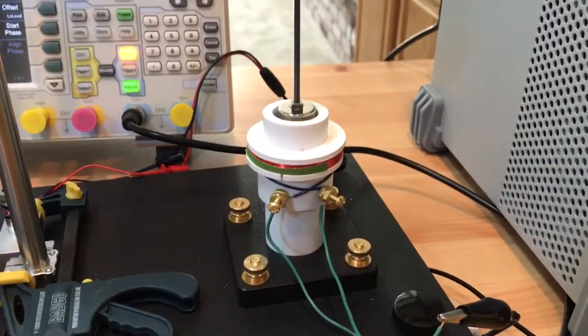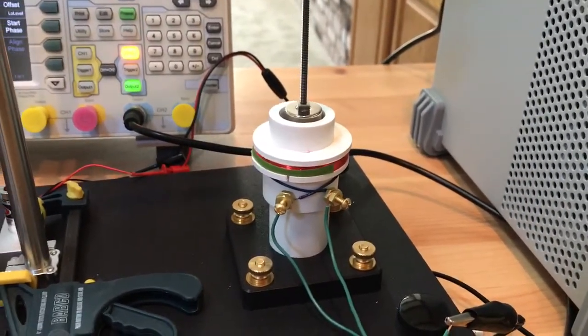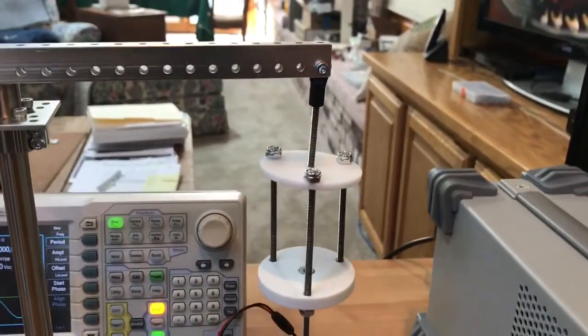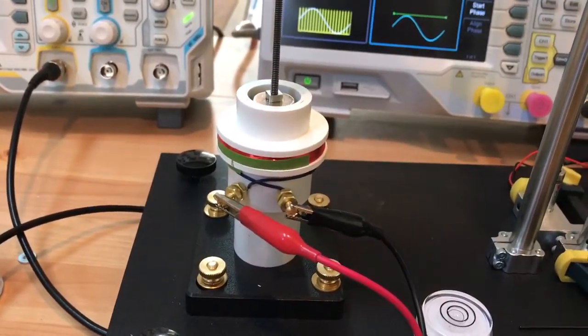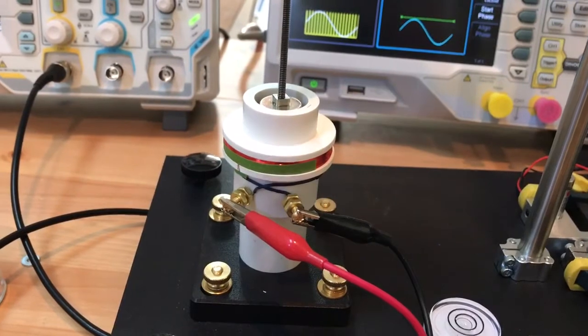The magnets are reacting to the current in the coil. This is the velocity mode, so the vertical velocity is translated over into the sensing coil magnets, and those magnets produce a voltage in the coil.